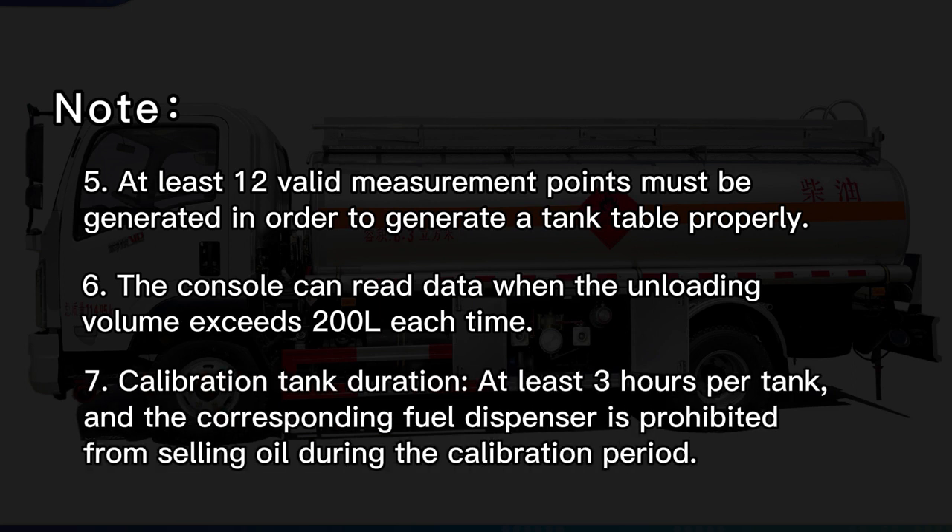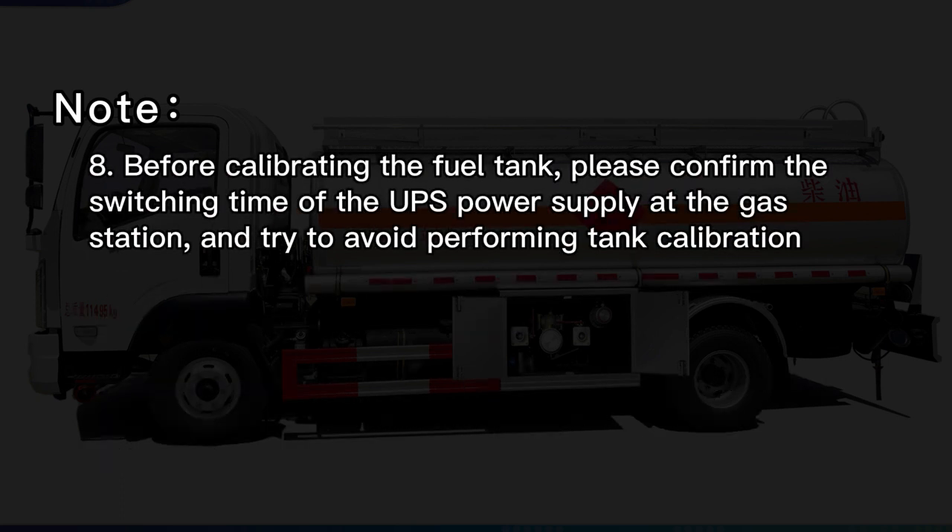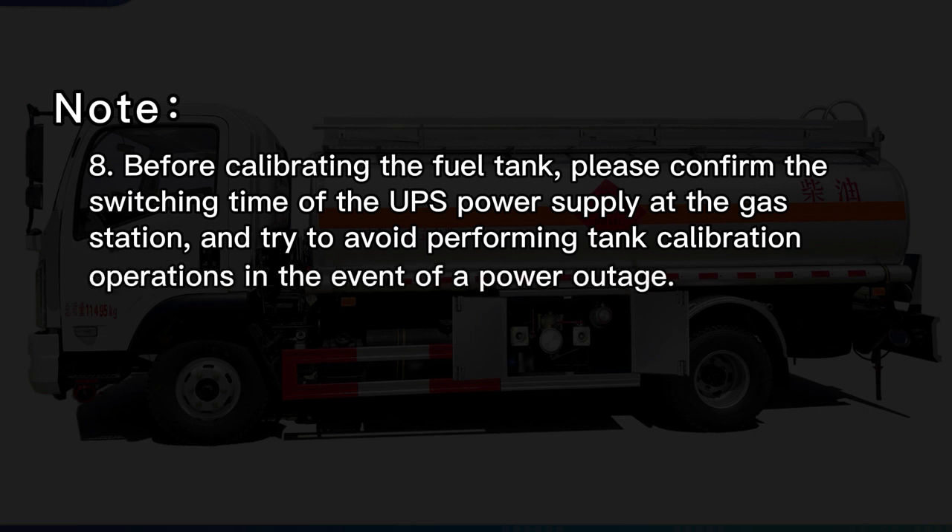Note 7: Calibration tank duration is at least 3 hours per tank, and the corresponding fuel dispenser is prohibited from selling oil during the calibration period. Note 8: Before calibrating the fuel tank, please confirm the switching time of the UPS power supply at the gas station and try to avoid performing tank calibration operations in the event of a power outage.